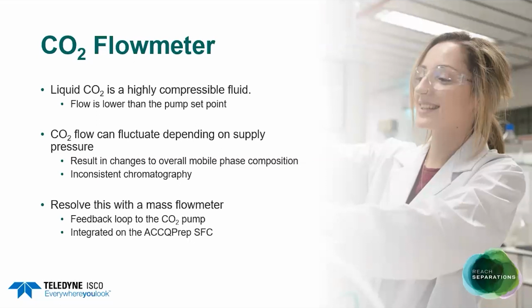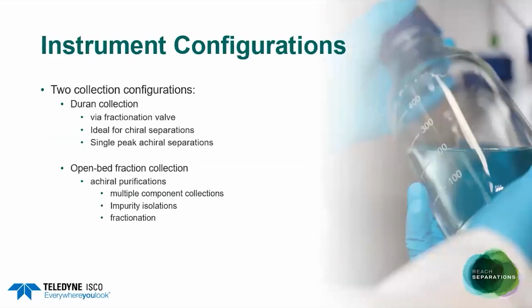Moving on to another feature of the ACCQPrep SFC, we have a CO2 flow meter built into the system. Now, liquid CO2 is a very highly compressible fluid. Now, the CO2 pumps on a system are actually adapted HPLC pumps. So the output flow you get is much lower than the pump set point. Another problem you can have is that the CO2 flow can actually fluctuate depending on what your supply pressure is. Now, what this can result in is changes in the overall mobile phase composition, which can lead you to inconsistent chromatography. The way you resolve this is by having a mass flow meter. And on the ACCQPrep SFC, this flow meter feeds back to the CO2 pump, and the CO2 pump speed adjusts itself to maintain a constant flow. And this is fully integrated on the ACCQPrep SFC.